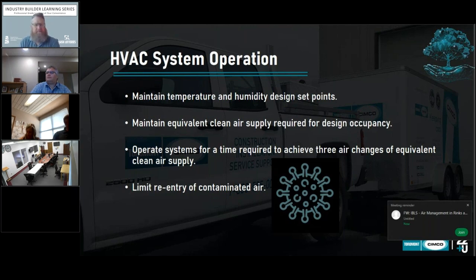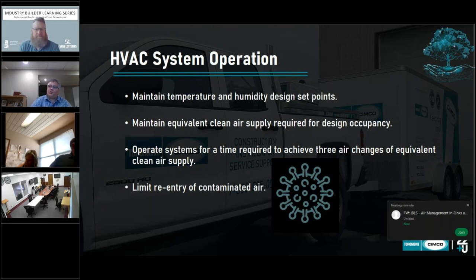So there's a cost, there's a challenge. And we really do want to control contaminated air, or the reentry of contaminated air. This is about return air systems, facilities that have return air systems or mixed air. That's what it really comes down to with COVID-19 and your HVAC systems - a lot of the conversations are about and around return air. So you need a good fundamental understanding and knowledge of what your systems do, how they operate, and what they're designed for.